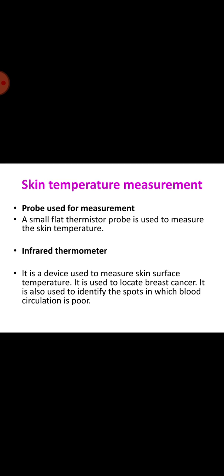And this infrared radiation can be used with a detector. The detectors used for measuring the emitted infrared radiation are thermopiles, pyroelectric sensors, gas cells, photoconductive cells, and photovoltaic cells. All these devices can be mounted in a specially designed housing to measure the surface temperature without direct contact with the body. Handheld infrared scanners are now available for monitoring the pattern of skin temperature changes, particularly for tympanic membrane temperature measurement.